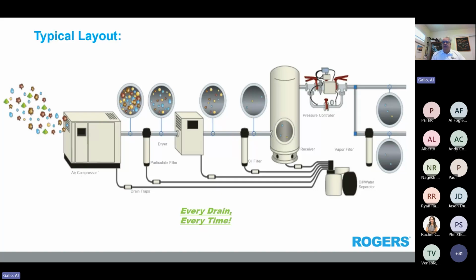Post filters clean it up even more, and then the dry air receiver cleans it up even more. It's allowed to cool down and stuff will start dropping out. Then we go out to the system through either the flow controller, so we are controlling the pressure in the shop, or we run it through a vapor filter. Activated carbon is pretty common. I used to sell a lot of these to distilleries and breweries and pharmaceutical companies, because they wanted absolutely clean air and did not want any hydrocarbons in there. But the one main thing, if you notice at the bottom of that picture, is all the drains from all the pieces of equipment going into an oil water separator.